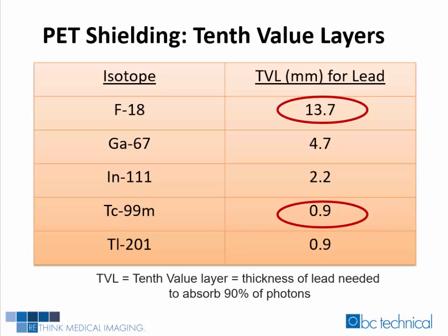When we talk about reducing our exposure from shielding, this is the put-up principle. This is clearly the most expensive of all of the principles, and not all shielding is created equal. The shielding needed for PET is many times thicker and much more expensive than the shielding you need for nuclear medicine. This slide shows the tenth value layer of lead for nuclear medicine and molecular imaging isotopes. The tenth value layer is the thickness of lead needed to stop 90% of the photons from penetrating the material. For technetium-99m, that value is 0.9 mm. For F18, the value is 13.7 mm. The takeaway here is that you need 13 times more lead to stop PET isotopes than with standard nuclear medicine isotopes.